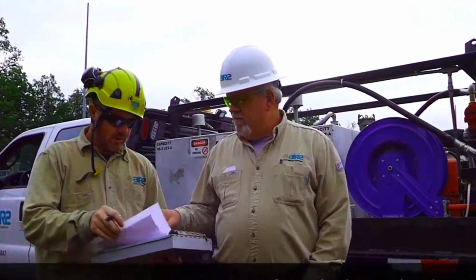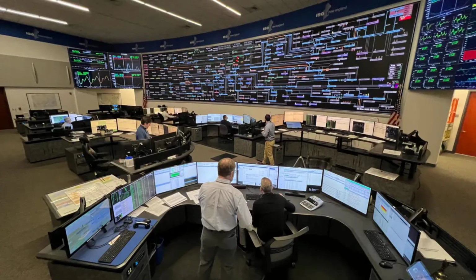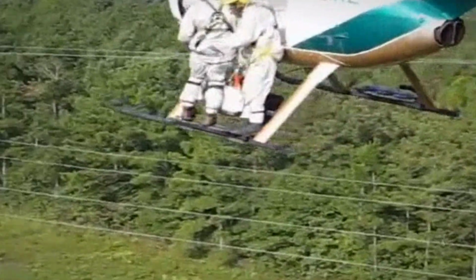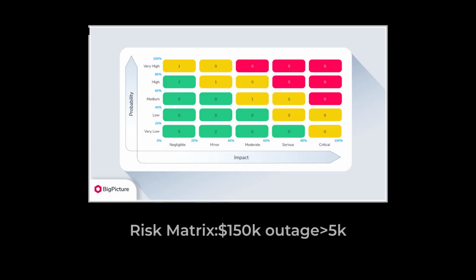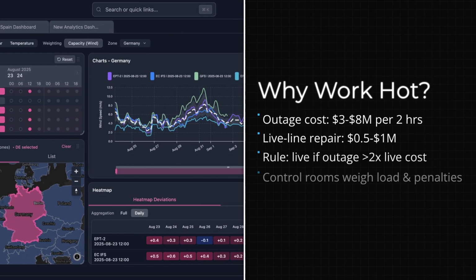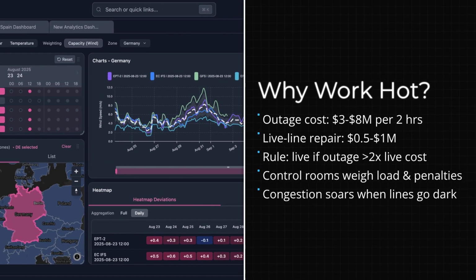The decision process is codified. If the projected outage cost exceeds twice the price of live work, the system defaults to keeping the line energized. This rule is enforced by automated risk matrices that weigh real-time load forecasts, reserve margins, and contractual obligations.